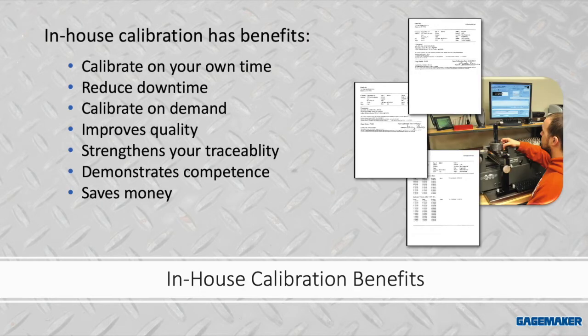Implementing an in-house calibration program has immediate benefits. Number one, being in control of your schedule and calibrating on your own time reduces downtime. If you have an urgent demand, say someone drops an instrument or something's been out of service and needs to be placed back in service, you have control in-house to handle that immediately without waiting on an outside service. It improves your quality, both directly and in the perception that you're demonstrating competence in your facility. It strengthens the traceability of your product through the inspection and calibration process. And bottom line, it saves money.